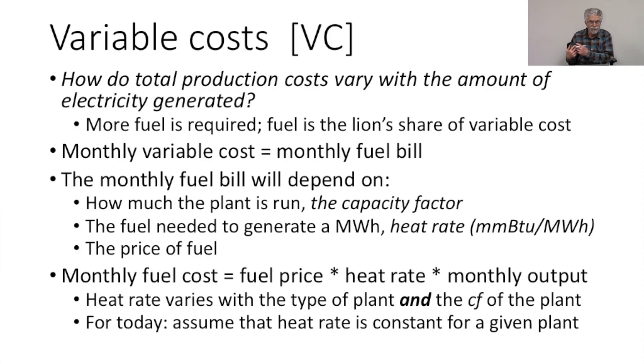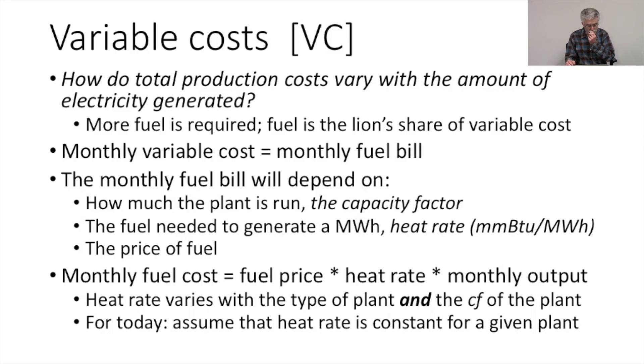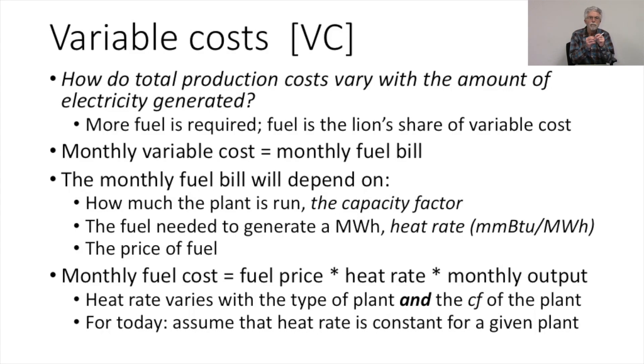Our monthly variable cost of operating the power plant is going to be our monthly fuel bill. So we need to think about how we calculate that. What does the monthly fuel bill depend upon? It depends on how much you run the plant — the capacity factor of the power plant — and it also depends on how much fuel is needed to generate each megawatt hour of output. That fuel requirement per megawatt hour, we have a term for that: we call it the heat rate.